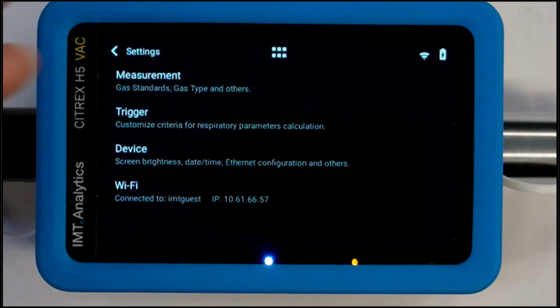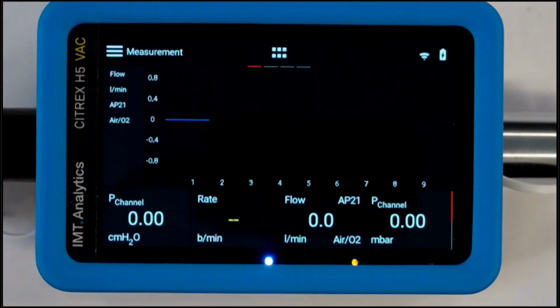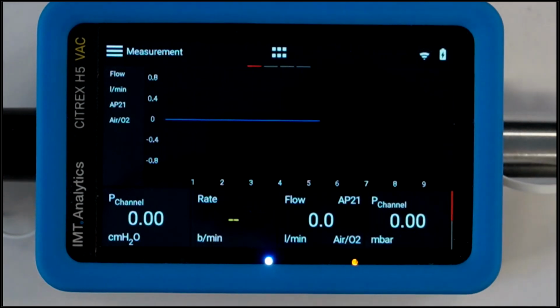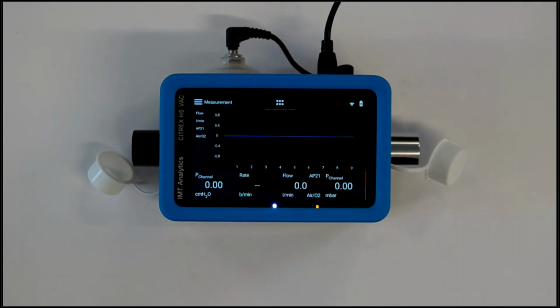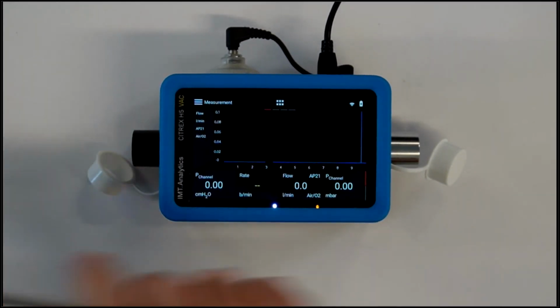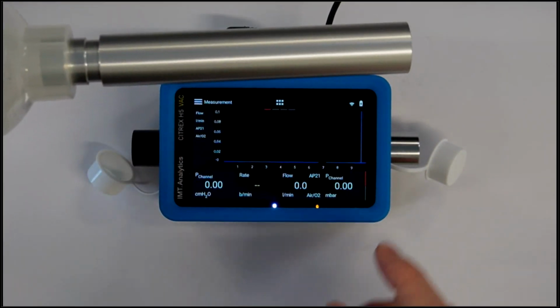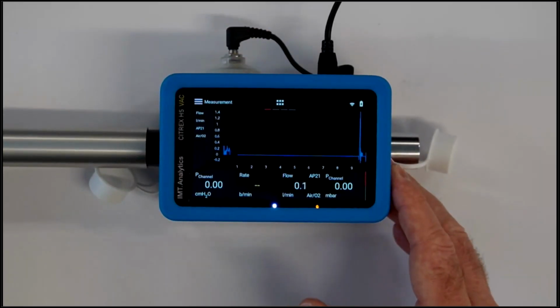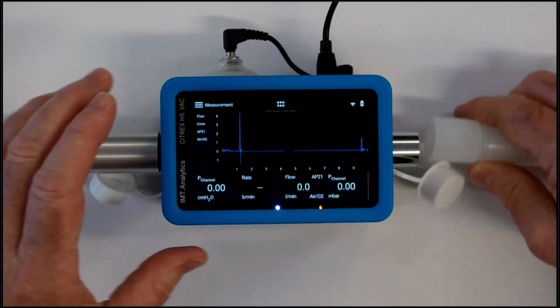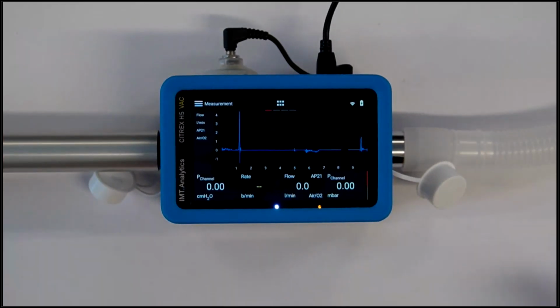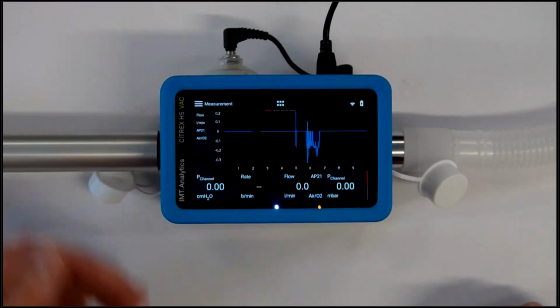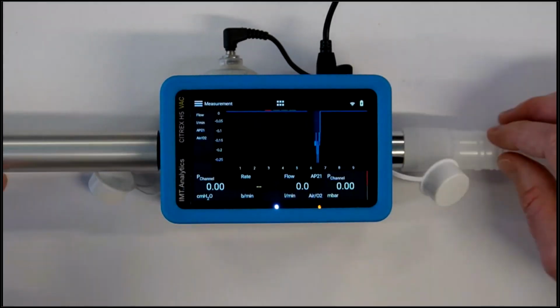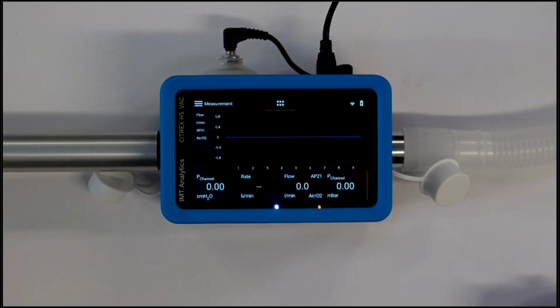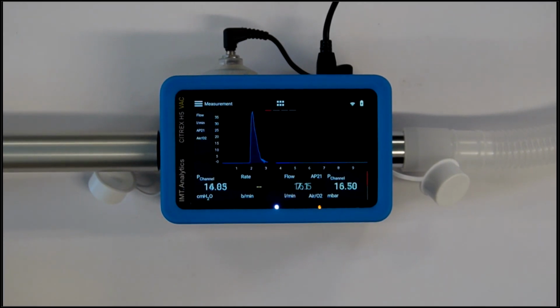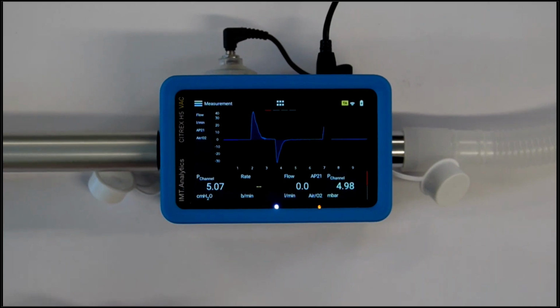Okay, so now that we have our device all set up and ready to go, I'll show you how easy it is to connect to our ventilator. I'll zoom out just a little bit here. So we just take our Y, attach, always with our filter, attach the flow tube to the input side of the H5. Connect the test lung to the output, and we're done. It's just that easy. As Daniel said, it's an all-in-one device. No teeing in pressures, no teeing oxygen. It's all taken through the main flow channel. Now, if I start ventilation, then we see that we get a nice waveform here on the first measurement screen, and we get numbers.